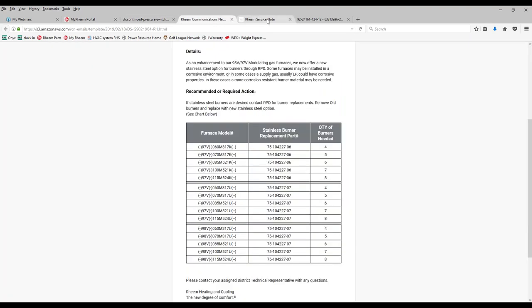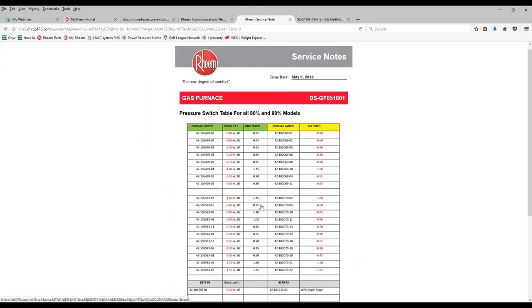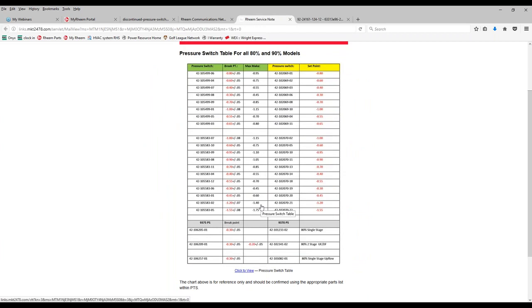We also have pressure switch tables for the new equipment and the part number and the break point and max make point of those. This as well will be coming out to all our Rheem and Ruud contractors. You will be seeing that probably next week when we get our communications sent out. And you'll see you can have the data plus or minus 0.05 and then be able to match it to the switch that you have. So if you got any questions on that, you can let us know after you receive it.